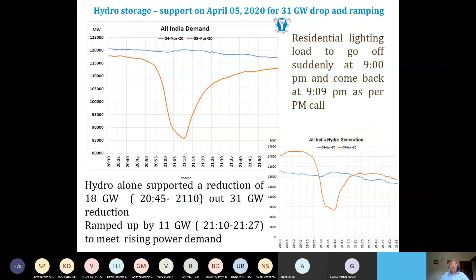Ramping of a hydropower plant can be 30%, 40%, even 50% per minute, compared to a thermal power plant where even 1% ramping per minute is considered very good. In fact, people currently only manage 0.5%, so regulators are now asking them to achieve at least 1% ramping, but ramping is not that easy. People have seen the wonder of hydropower.